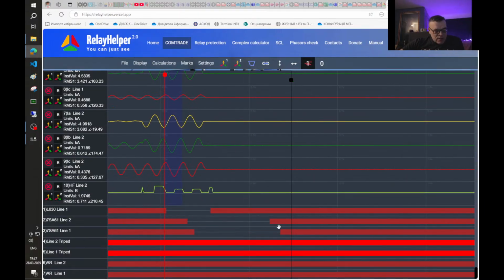One moment about the digital fault recorders. It's also from our Ukrainian manufacturer, and it has its own software, but it has an issue that when it transfers a file to COMTRADE format, it inverts digital signals. So when it shows zero, that means that the signal was asserted.